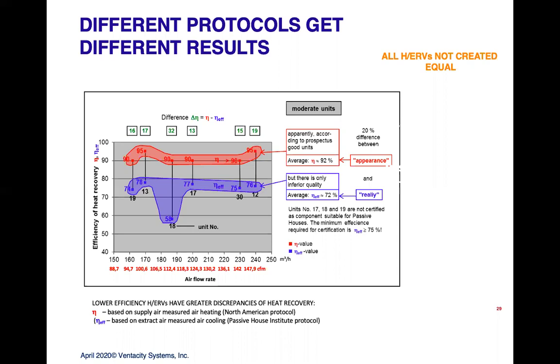the building at 40 degrees, that's a 10-degree delta T, and it's going to be 1.08 BTUs per cubic foot per delta T of temperature in Fahrenheit. So 10 times 1.08, and if we're running at 500 CFM, that's going to work out to somewhere over 5,000 BTUs an hour leaving the building on one 500 CFM unit. So passive house is a much better metric for applying to an energy model to understand what the energy losses are on that whole building as a system than HVI or AHRI.